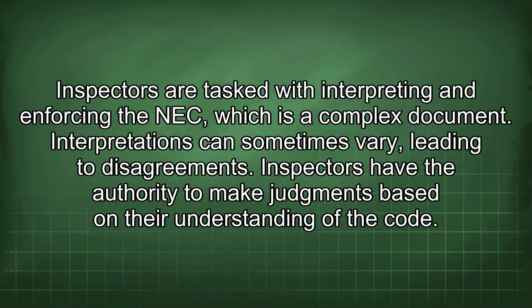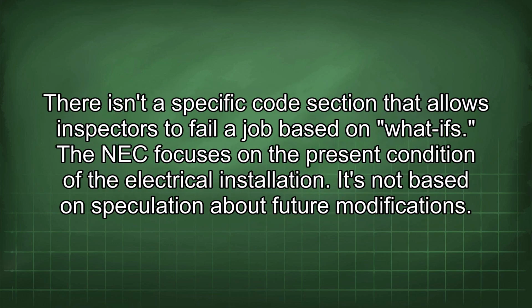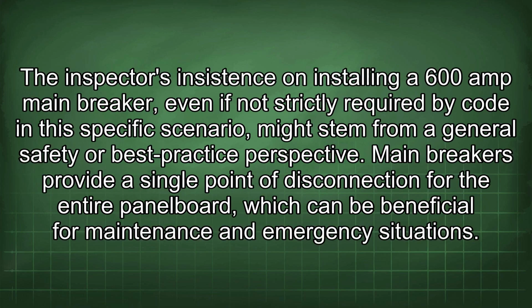Inspectors are tasked with interpreting and enforcing the NEC, which is a complex document. Interpretations can sometimes vary, leading to disagreement. Inspectors have the authority to make judgments based on their understanding of the code. There isn't a specific code section that allows inspectors to fail a job based on what-ifs. The NEC focuses on the present condition of the electrical installation. It's not based on speculation about future modifications. The inspector's insistence on installing a 600 amp main breaker, even if not strictly required by code in this specific scenario, might stem from a general safety or best practice perspective.